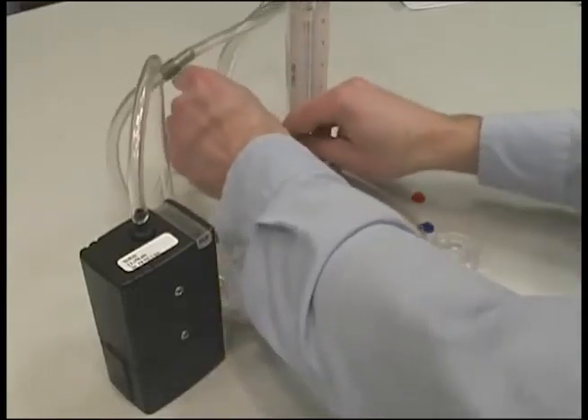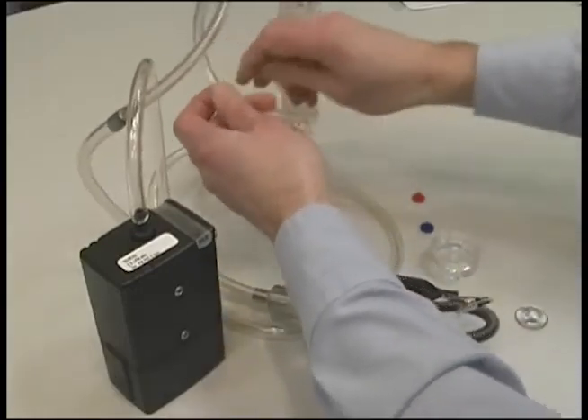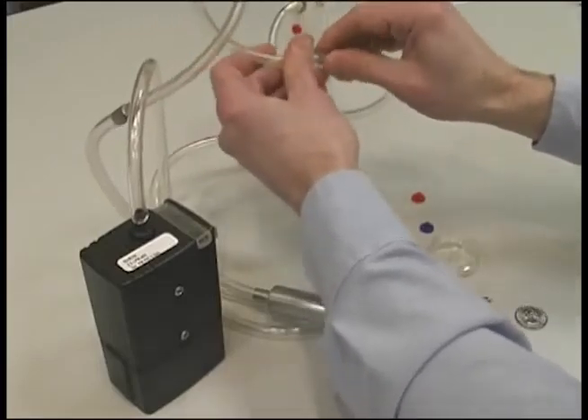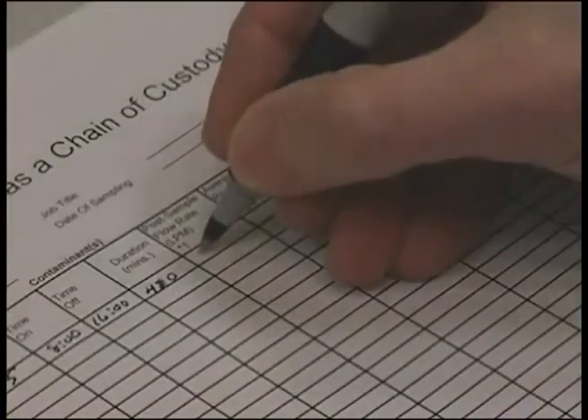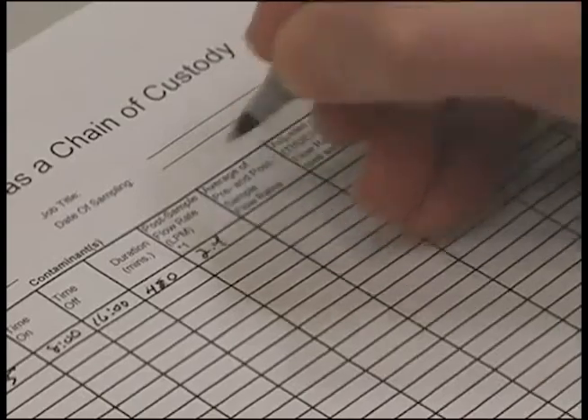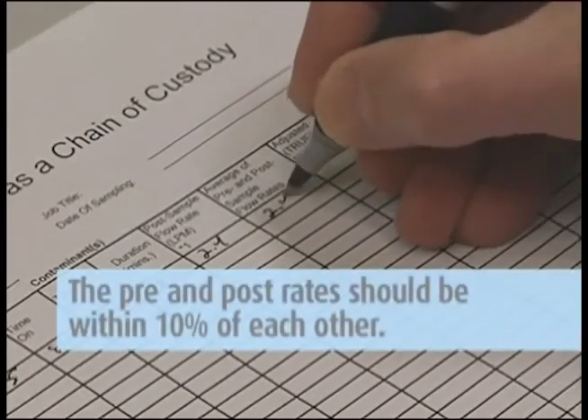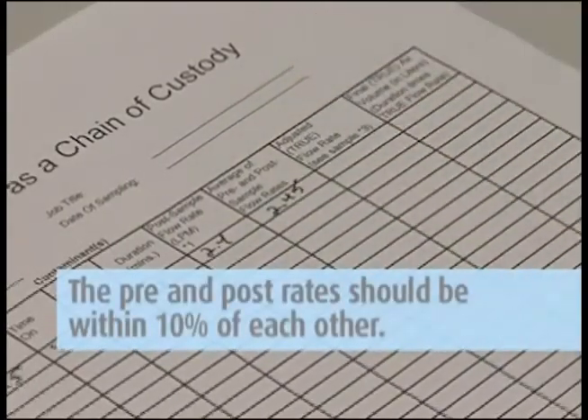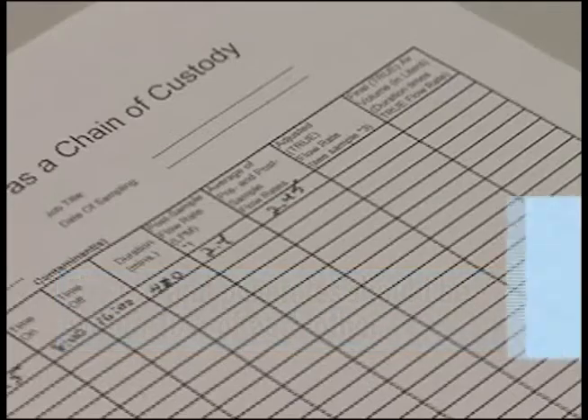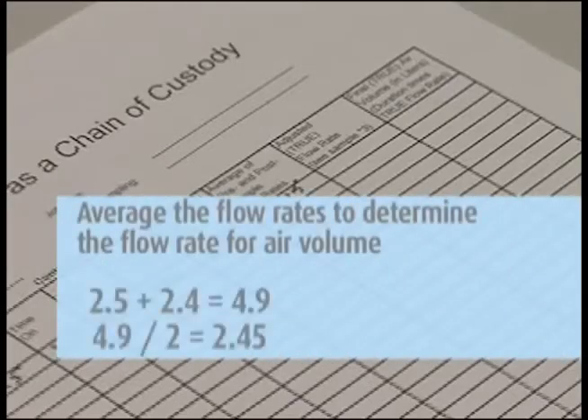Perform the post-calibration the same way you did the pre-calibration, using the marked calibration cassette, but do not make any adjustments. Just record the flow rate on the pump calibration sheet. The pre and post rates should be within 10% of each other. If they are, average the flow rates to determine the flow rate to be used to calculate the air volume.